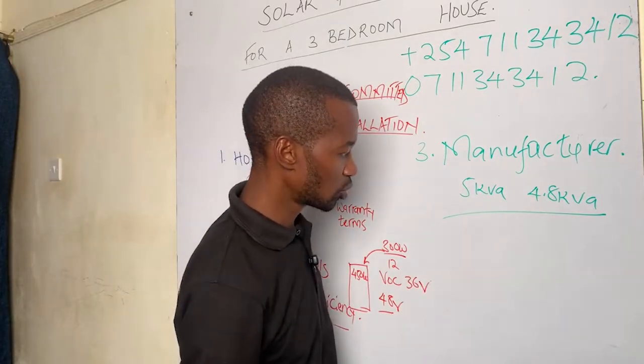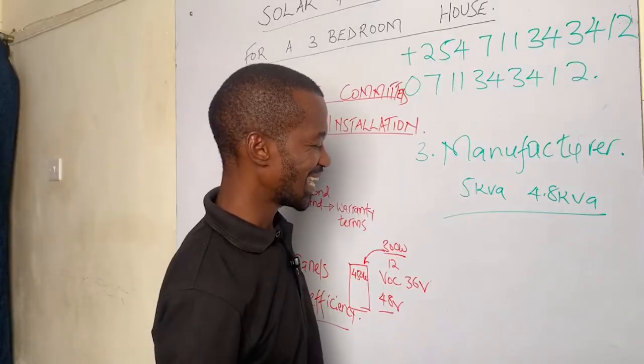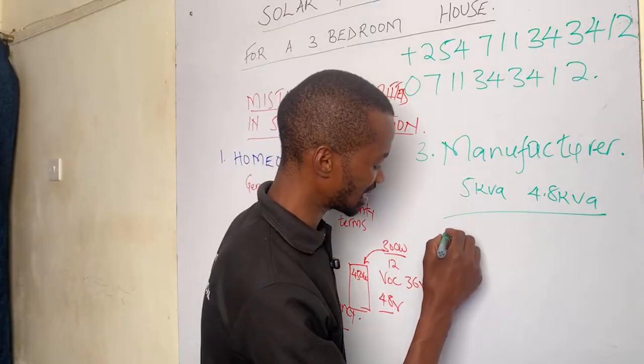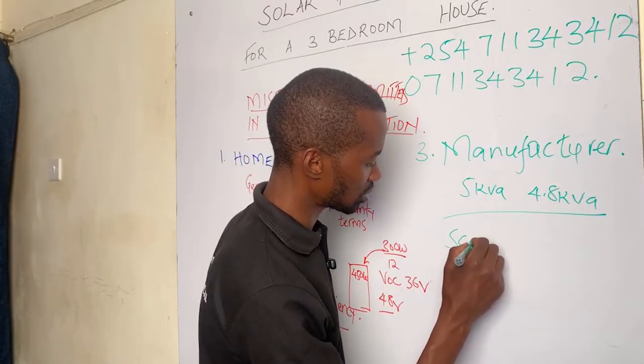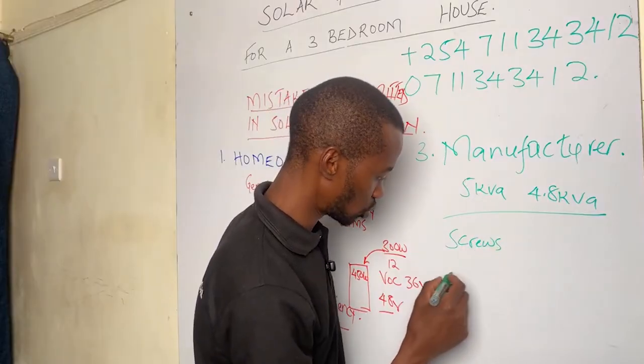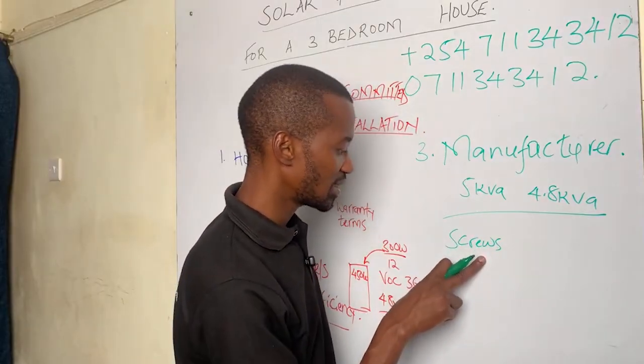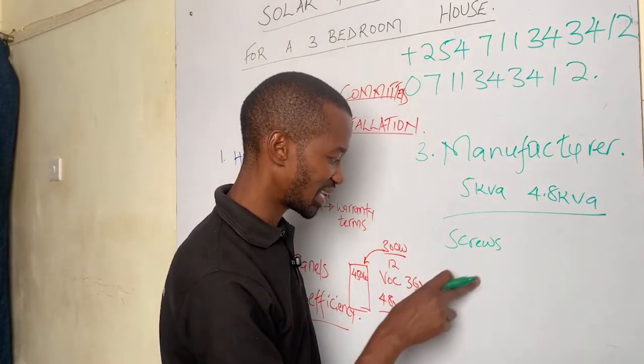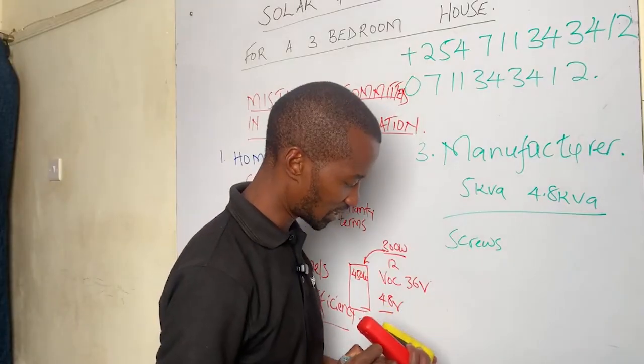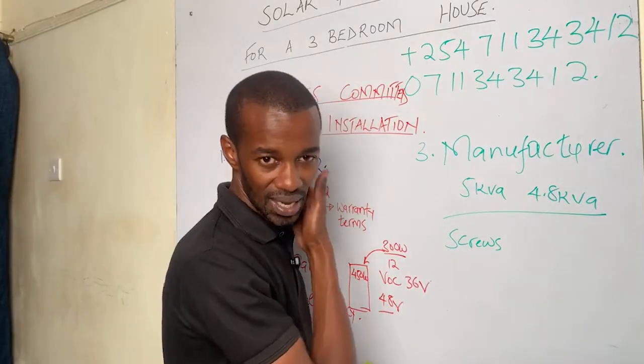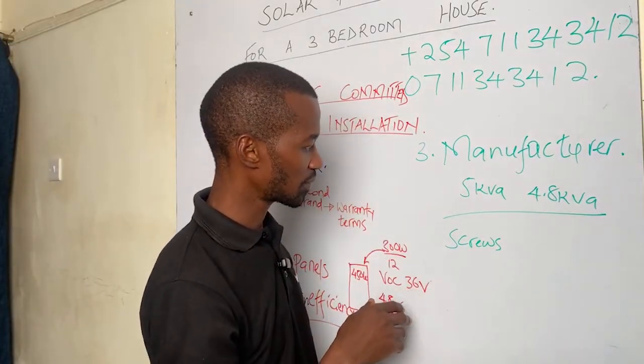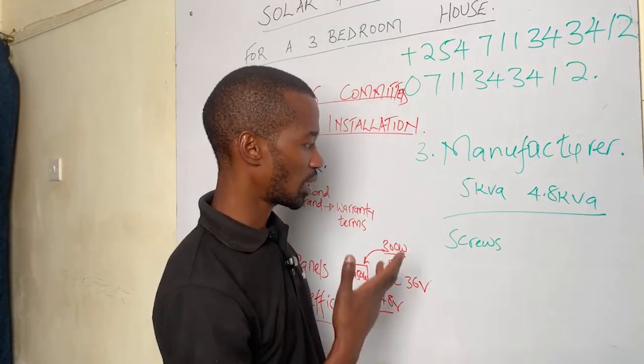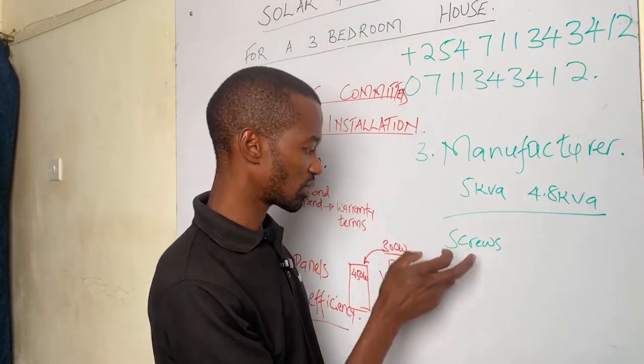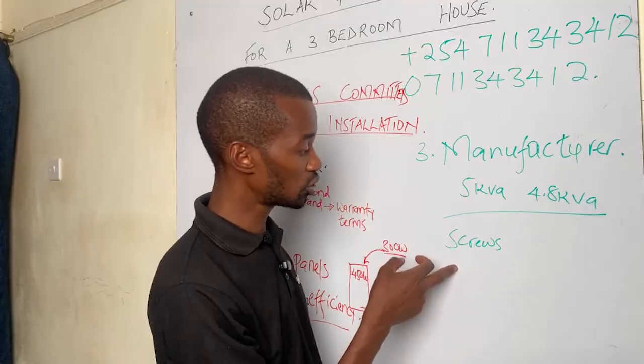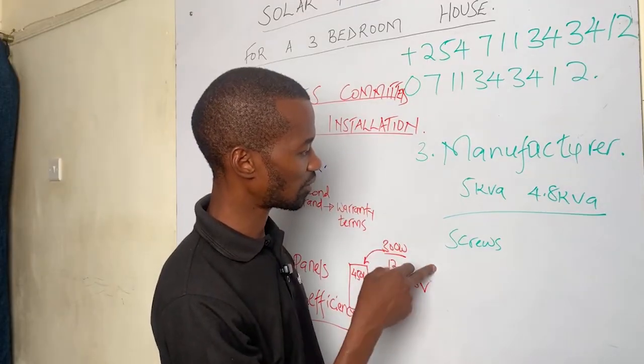Another important thing to note is what happens upon tightening the screws. This is where the majority of solar power issues occur. Upon tightening the screws, they get to a point where they start sliding. You try to tighten and then it starts to slide, and the electrician gets confused about what to do. That is a heavy mistake, especially from the manufacturer side.